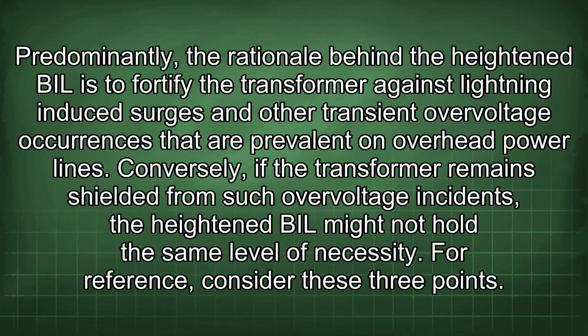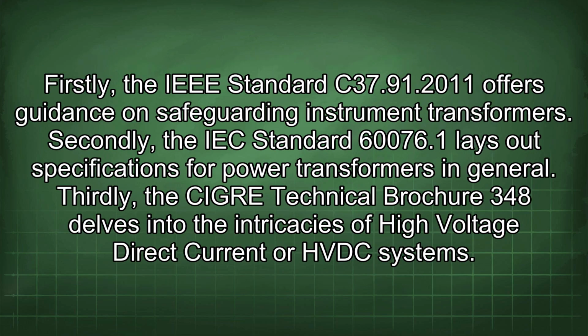Conversely, if the transformer remains shielded from such overvoltage incidents, the heightened BIL might not hold the same level of necessity. For reference, consider these 3 points. Firstly, the IEEE standard C37.91/2011 offers guidance on safeguarding instrument transformers. Secondly, the IEC standard 60076.1 lays out specifications for power transformers in general. Thirdly, the CIGRE Technical Brochure 348 delves into the intricacies of high-voltage direct current or HVDC systems.